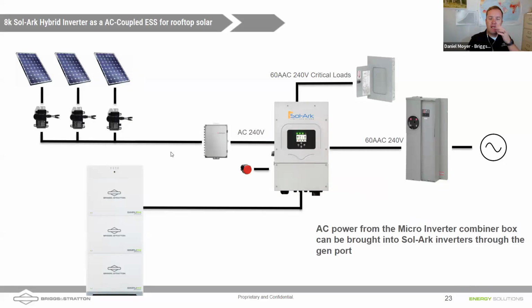So this is what it looks like when we're bringing in AC. Remember, we have that AC, those micros, the IQ Combiner, and now we're bringing that into the Sol-Ark on the gen port right here. And then what we have is still our battery right here. Now notice, and I could have done this on the other slide, that when we're backfeeding, say, a load center with a 200 amp main and a 200 amp bus, the NEC 120% rule says the largest backfed breaker we can have is 40 amps.